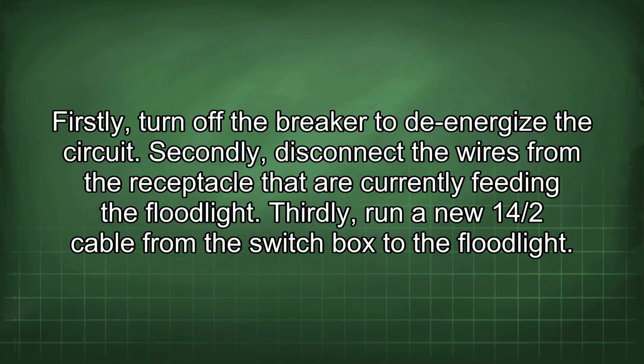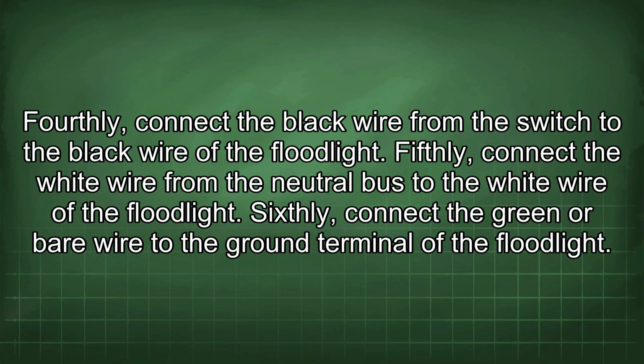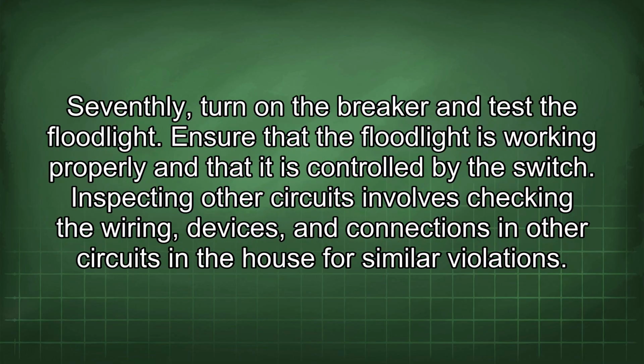Thirdly, run a new 14/2 cable from the switch box to the floodlight. Fourthly, connect the black wire from the switch to the black wire of the floodlight. Fifthly, connect the white wire from the neutral bus to the white wire of the floodlight. Sixthly, connect the green or bare wire to the ground terminal of the floodlight. Seventhly, turn on the breaker and test the floodlight. Ensure that the floodlight is working properly and that it is controlled by the switch.